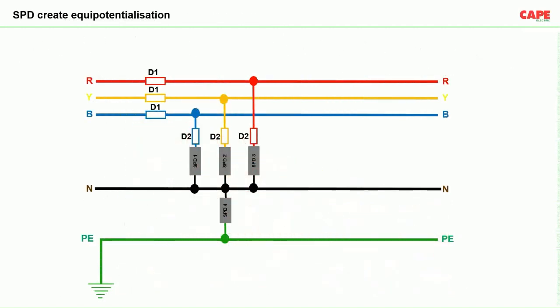Now, how do we connect an SPD in an electrical system? Suppose we have a 3-phase system — R, Y, B, neutral, and protective earth. There are two methods: a 3+1 connection and a 4+0 connection. For explanation purposes, we have taken a 3+1 connection, where 3 SPDs are connected between line and neutral, and the 4th SPD is connected between neutral and earth.